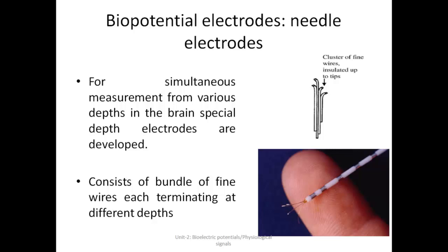In this type of electrode, the metal electrolyte interface takes place between the insulated tip of the wire and the electrolytes present in the human body. The needle electrodes that create the interface beneath the surface of the skin seem to be less susceptible to movement limitations than the skin surface electrodes. By making direct contact with the subdermal tissue or the intercellular fluids, these electrodes also have lower impedances as compared to the surface electrode.